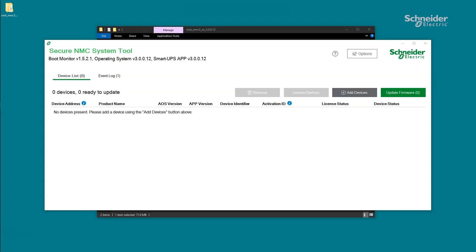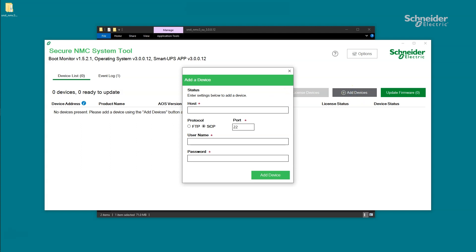After unzipping the Secure NMC System Tool and loading the tool, you can now add devices. To add one at a time, click Add Devices and enter the NMC's IP address, FQDN, and Host Name. Then enter the protocol and port to transfer the firmware file. SCP is recommended as it is more secure than FTP. Note that the selected protocol must also be enabled on the NMC3. And lastly, enter the username and password, then click Add Device.